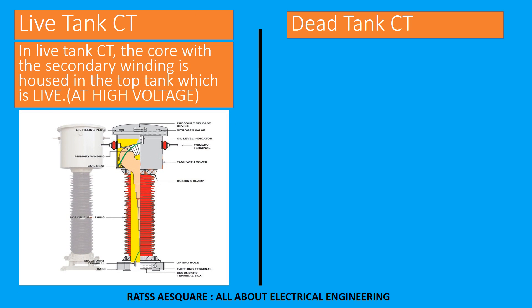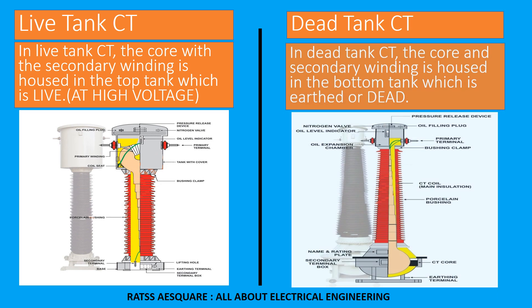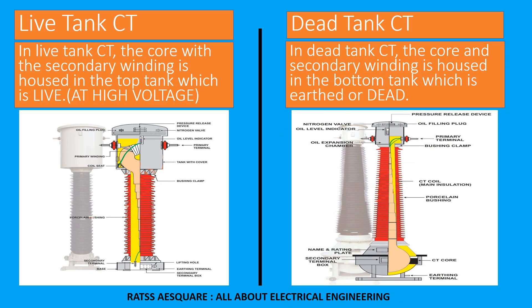In live tank CT, the core with the secondary winding is housed in the top tank, which is live at high voltage. In dead tank CT, the core and secondary winding is housed in the bottom tank, which is earth or dead.